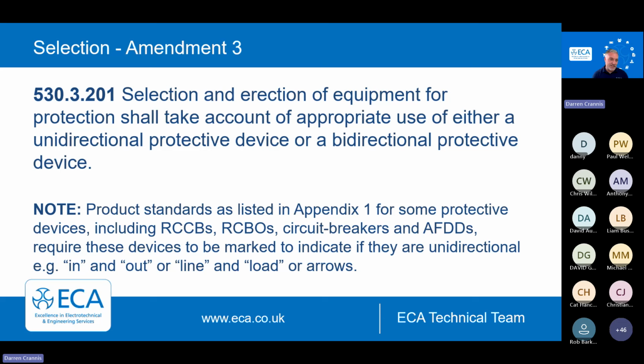This isn't just BS 88 fuses, which are bi-directional anyway. This is MCBs, so circuit breakers, RCDs, RCBOs, even MCCBs and ACBs. So it's best that you talk to the manufacturers, depending on the frame size, and find out if they can take energy both ways and what the restrictions are. For example, MCCBs and ACBs may be bi-directional, but can only take fault up to certain fault levels in certain directions. So if you're building panels, consider that. If you're in domestic and commercial installations, just be aware that if you've got energy flow going both ways, you'll need a bi-directional device. They're very, very common now, and they've come right down in price. I think they're near on the cost of your traditional RCDs, for example.